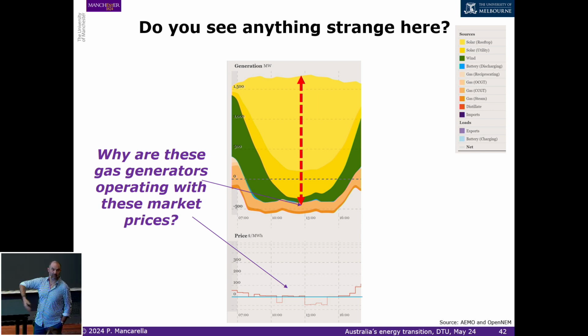But there are things that at the moment technologies are really not very good to provide, which is the so-called system strength services. Starting from short circuit current to effectively all voltage stability services, this idea of forming the grid, forming the voltage in a very nice shape of the voltage waveform. At the moment, this is done by synchronous machines. The moment synchronous machines disappear, you need someone to actually form the grid.